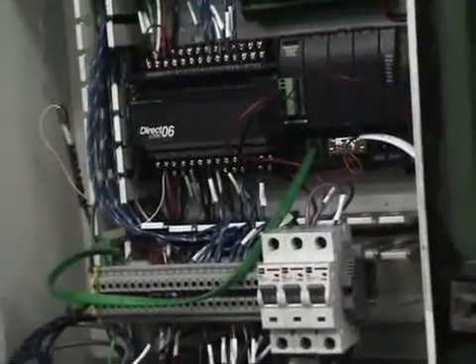Your first Rebeamer upgrade began with a plan to retrofit one of the Rebeamers with a DirectLogic Micro PLC, a DuraPulse AC variable frequency drive, and a C-more operator interface panel. What drove that decision? Actually, the first Rebeamer we kept DC. We started out with a cabinet full of relays — just old-fashioned relay logic. We stripped all those out and put one small DL06 PLC in, which took the place of all of them, but we still kept the DC, changing to a later drive since the original was obsolete. Those drives had 100% turnover in the first year — they all failed. Then we went to another drive, but they stopped making those in 230 volts, which is what we required. So we finally went with AC drives and motors, and it's a big difference.